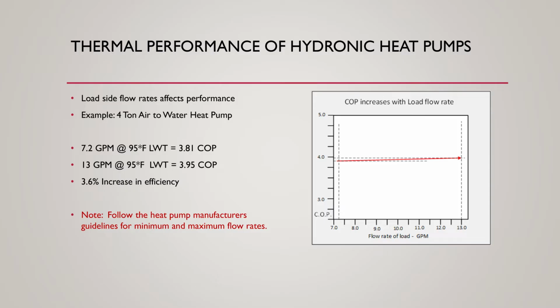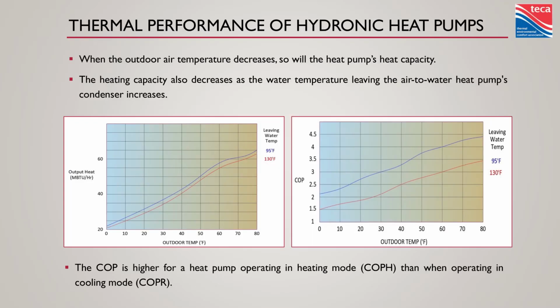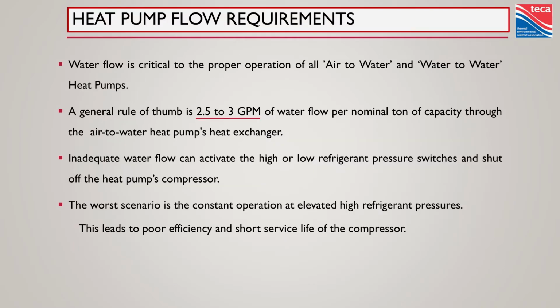So, a couple of slides illustrating some of the differences in efficiency just by changing the leaving water temperature. Right here on the right, I've got outdoor temperature left to right from cold to warm. On the left-hand axis here we have COP, so higher on the scale, more efficient. Got two lines here, a blue one and a red one. The blue one is a 95-degree leaving water temperature in Fahrenheit, and the red one's 130. So 130 is not that hot in the scheme of hydronics, but there is a massive change in efficiency just by dropping 40 degrees on your leaving water temperature. Do that all the way across the heating season, and there are some significant advantages to low temperature hydronic heat emitter design. Let's talk flow rates.